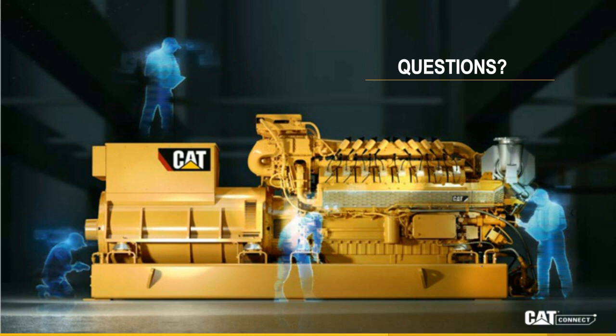I don't know if that was clear, but I'll take a stab at it from a hardware perspective. You're looking at probably between $700 to $1,500, round numbers, just for the genset hardware. Then, going back to the configuration file, that might take a few days of engineering work. After that, there are the subscriptions. The most common commercial model is a subscription, a monthly charge that varies across vendors in the industry, somewhere between $10 to $100 or $150, depending on the amount of data and frequency of data per month.